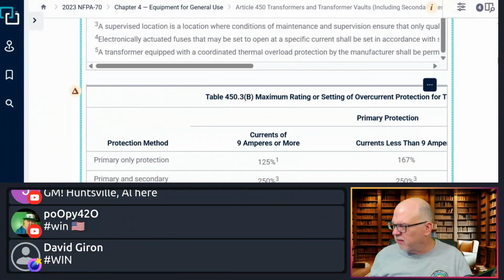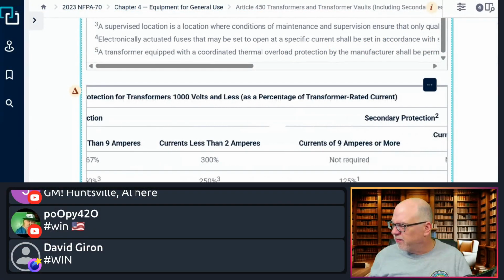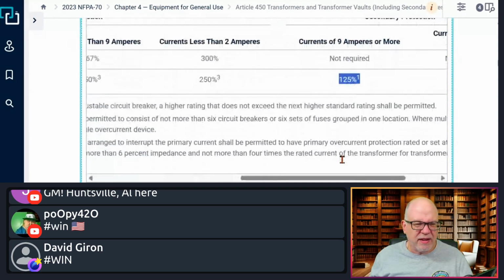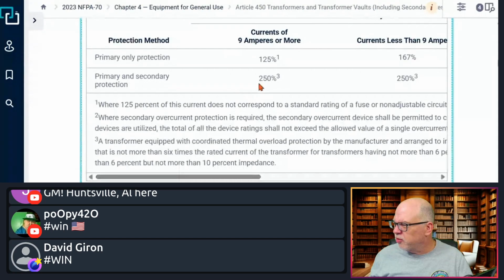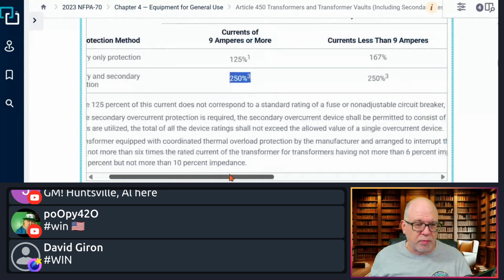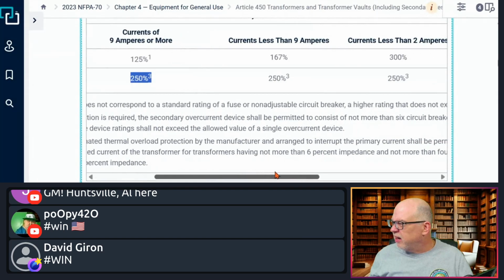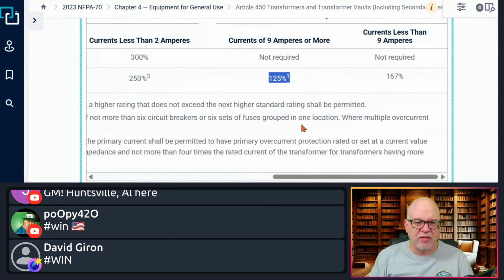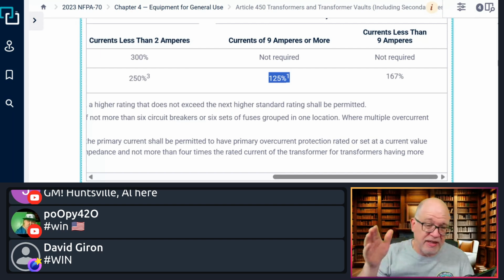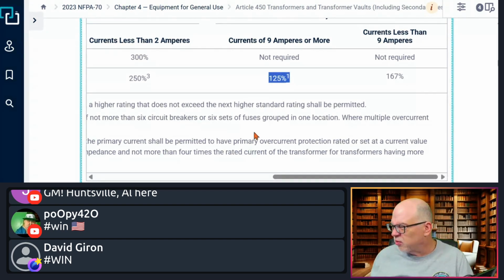On the secondary side, if they're doing it at 125% and it does not correspond, then you have a note there that is very similar. I'll take you here, and here's your note, right here. And there's your note right there. So here you see your primary up to 250%. Again, this is for currents 9 amperes or more, which is probably most of what you're dealing with. And then over here, you see 125% is the secondary protection of that transformer, not to exceed 125%, but we have a note. Note 1 says if you go to 240.6 and it doesn't correspond, I'll let you go to the next size. That's fine. Just can't exceed the next size, but I'll let you go to the next standard size. That's what it's talking about there.